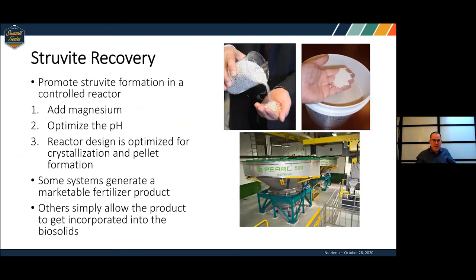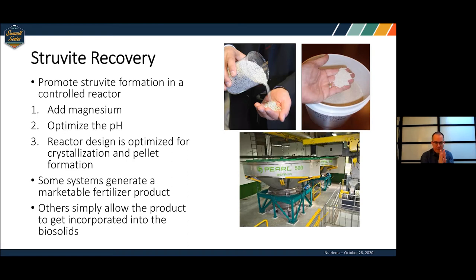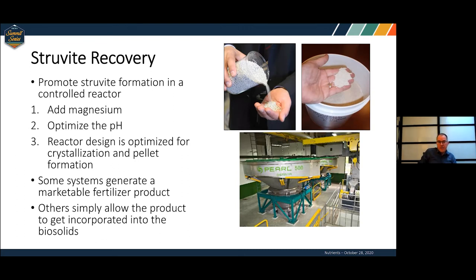A number of vendors have come out with struvite recovery processes. The way these work is they're actually trying to form struvite intentionally — picking a point in the treatment process, adding magnesium, optimizing pH, and designing a reactor optimized for crystallization and pellet formation. Some systems generate a nice fertilizer product. Others allow the struvite to go into your biosolids, giving you an essentially fertilizer-enhanced biosolids product.